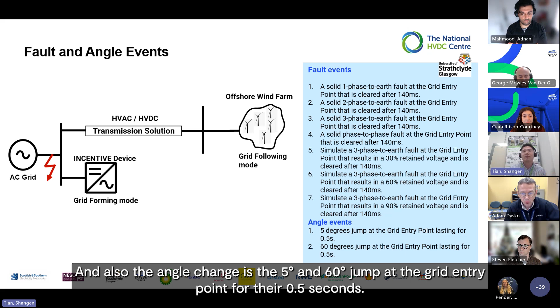Apart from frequency events, there are also testing events for fault and angle, which are very useful. For the fault event, we simulate different types of faults to examine the performance and response from the device. The angle change test is a 5 degree and 60 degree jump at the grid entry point for 0.5 seconds.